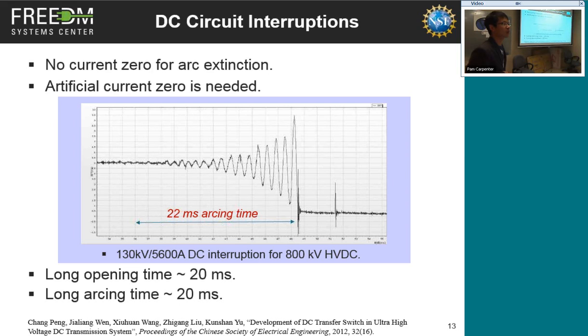So what happens now is we use some alternating circuit to try to create a current zero. This alternating current circuit has some very subtle interaction with the arc. The arc itself is very complex, but it has a tendency of instability. It has very strange VI characteristics. It's negatively resistive. So when you put that into an oscillating circuit, something happens like this. The arc current will oscillate, and not only oscillate, it will be amplified. The oscillation is being amplified, and it goes up and down, up and down. So here is 5-something kiloamps, and you will oscillate, oscillate. Okay, at this moment, it oscillates, it comes to a current zero. Okay, you got it. Then the circuit is interrupted. The arc is extinguished, and mission completed.